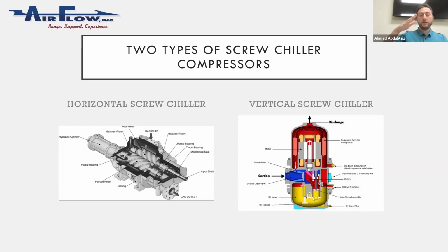If you look at the conventional horizontal screw, it has two rotors—we call them male and female. In the single screw design, you have one main rotor, then two small circular pieces called gate rotors, one on each side. When it moves, those two gate rotors perform the compression. You have a bearing here, a bearing here, a bearing here—so you'll have more bearings compared to horizontal screws.